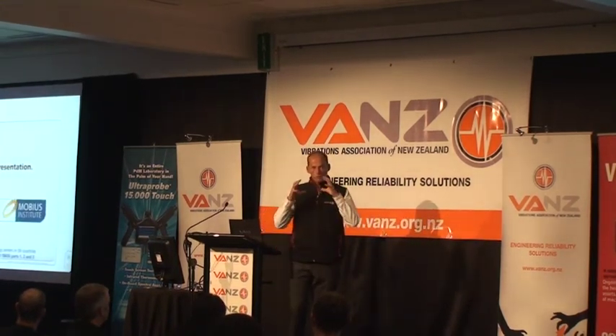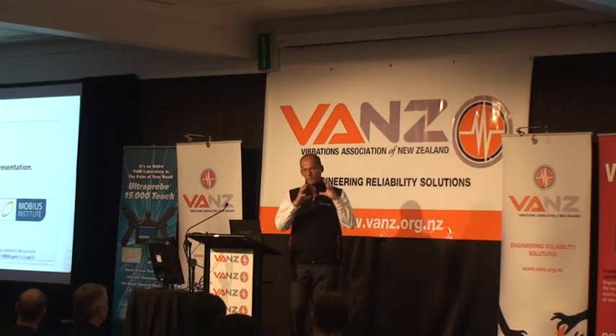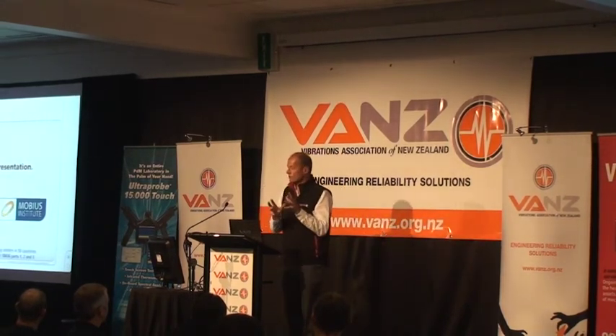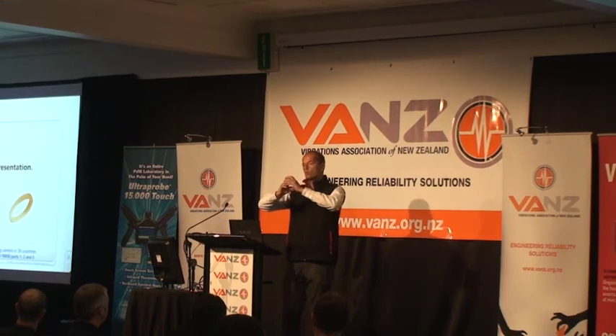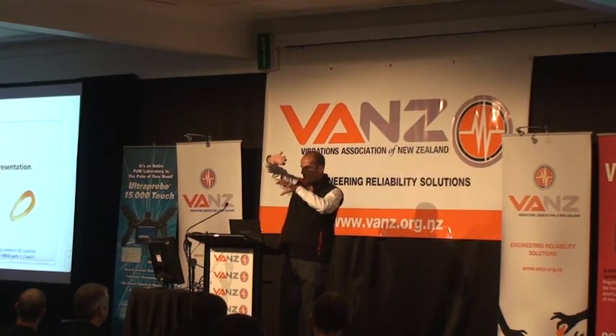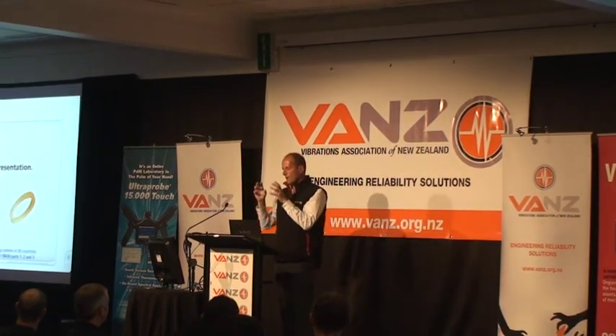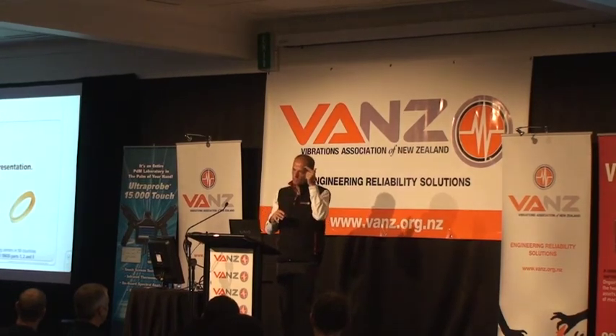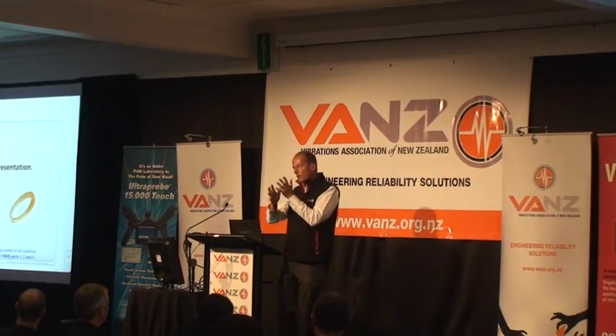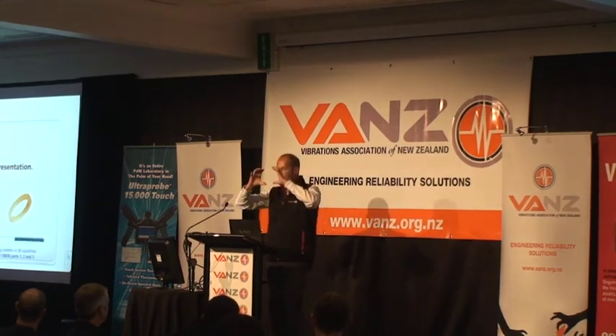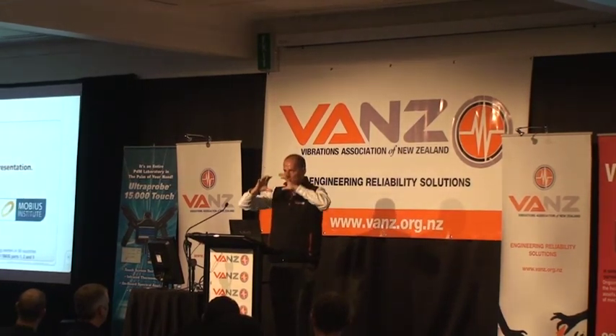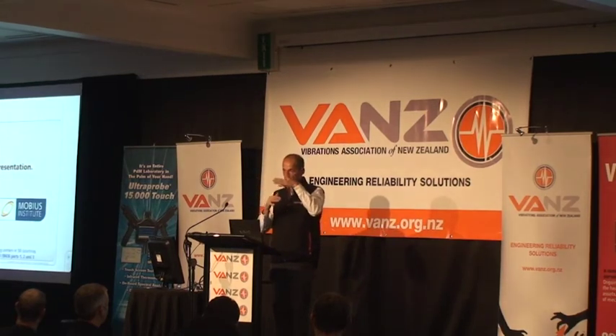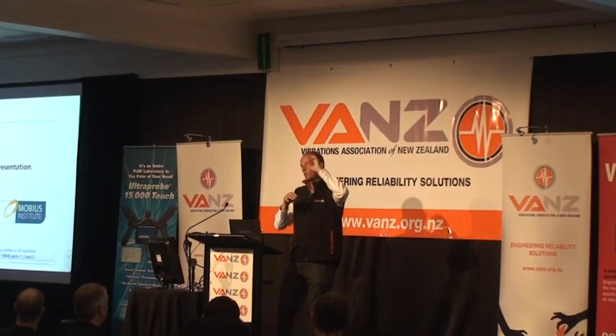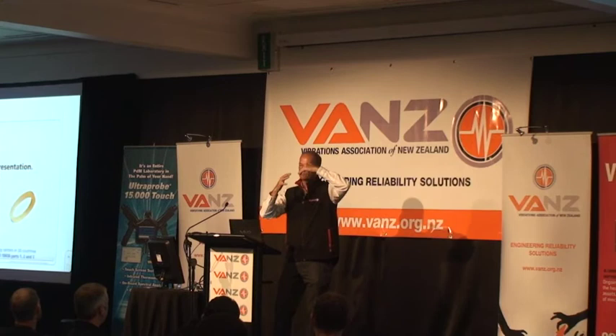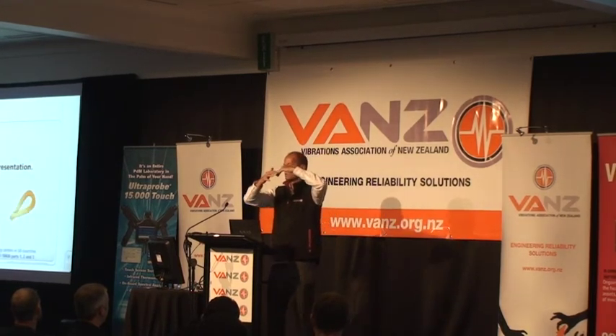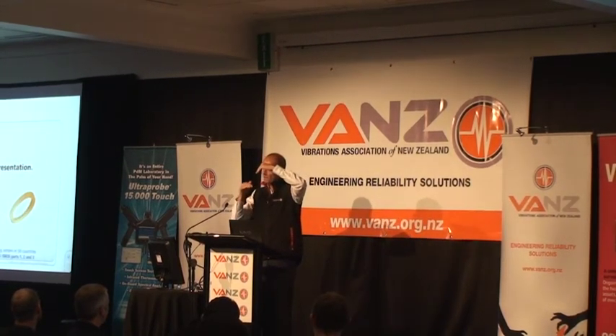But I think, if you're trying to see what the shaft is doing within the bearing, one question that comes up so frequently is, if you took an accelerometer and put it on the outside of the bearing and double integrated it down to displacement, would you see the same as what you see with a prox probe? Now, although they're both integrated to displacement, one is looking at the displacement of the bearing cap, and one is looking at the displacement of the probe, which is probably physically attached to the bearing cap. Again, we could talk about this forever, but looking at that relative movement to the shaft.